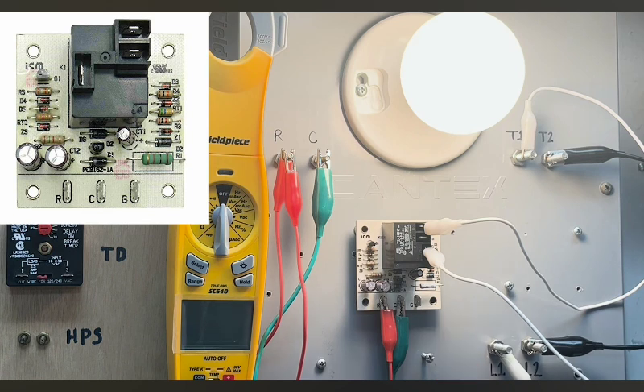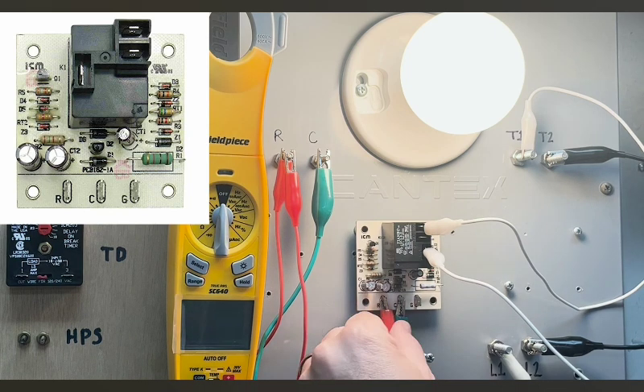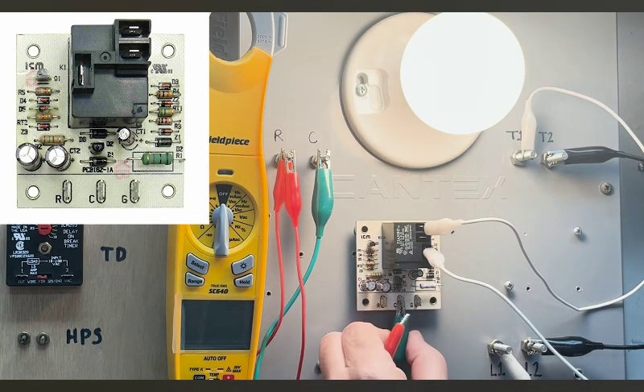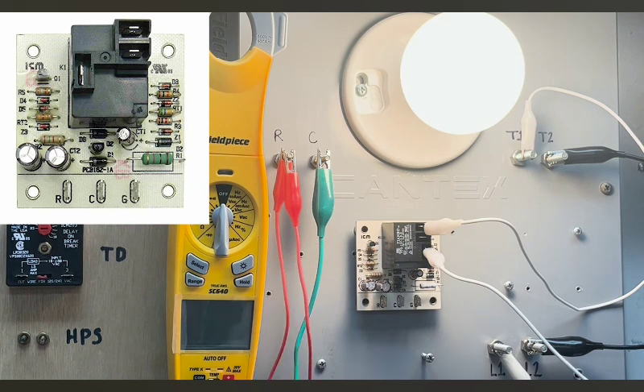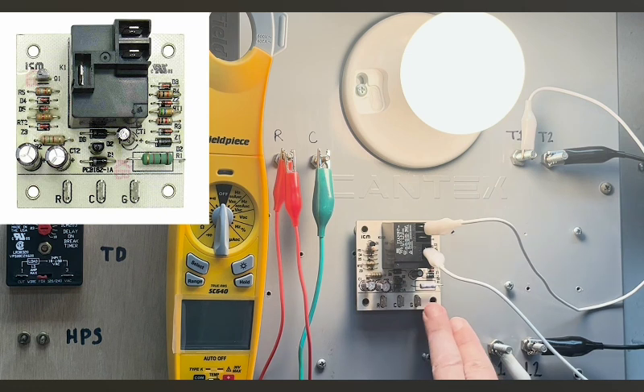Now I don't need a G call. This load is running without a G call. And now I can take all these other wires off of this here. And basically, it's normally closed. And so I don't need any low voltage for that relay to be normally closed. However, if I applied voltage between R and C, and I applied voltage to G and then dropped it out, I will have a 50-second delay there.